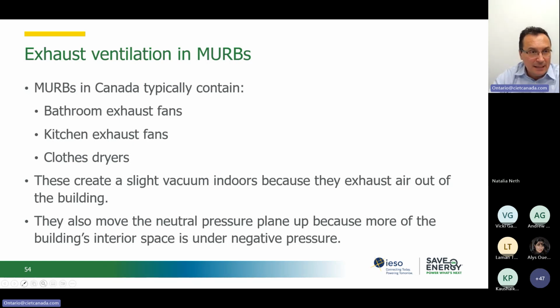We have to maintain the building pressurization. In multi-unit residential buildings, we have bathroom exhaust, we have kitchen exhaust, we have dryers exhaust in some installations where the units have the laundry equipment. So the balance of this is very important, and having exhaust leaving the space means that we are removing also energy. That air that we remove for the exhaust is already conditioned to the space requirements, and bringing fresh air to replace it will need the conditioning as well.